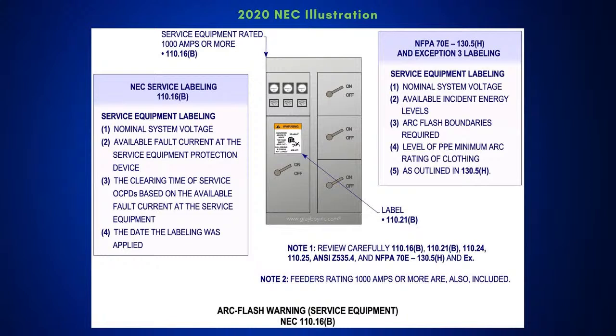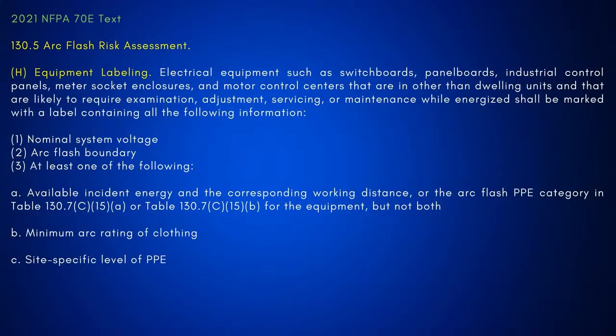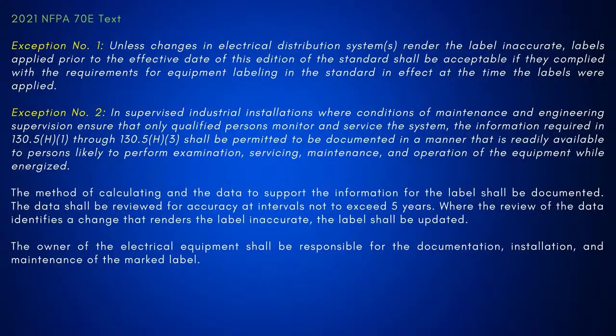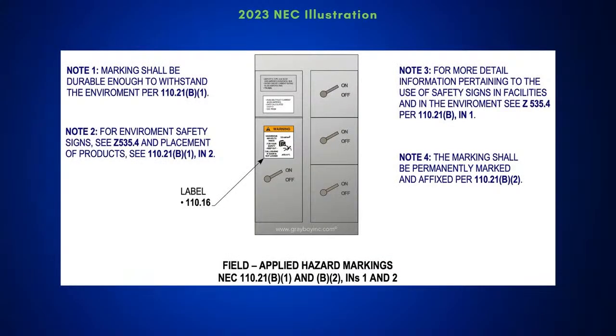So let's take a look at that for a second. Now, I just gave you what the 70E document requires. So what differs from 110.16B? Well, I've got the available fault current, the clearing time, and the date the labeling was applied. Those will be three extra that go on top of what's required in the 70E label. See that? Okay.